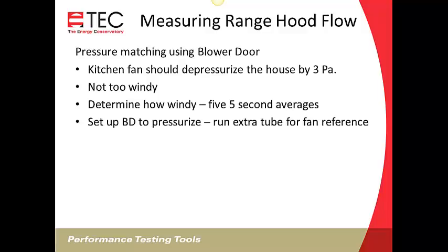Then we'll set up our blower door to pressurize. If you haven't done this before, it involves turning the Duct Blaster Fan around. We're going to be using the Duct Blaster Fan to measure flow, so we can't use the reverse switch. If you've got an older fan with a reverse switch, you can't use that reverse switch to measure airflow. And in this case, we're using the fan to measure airflow.